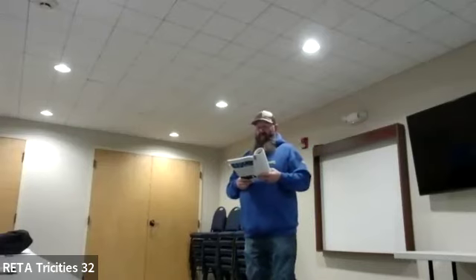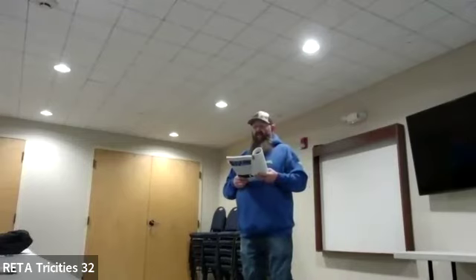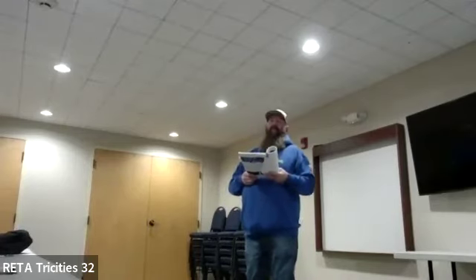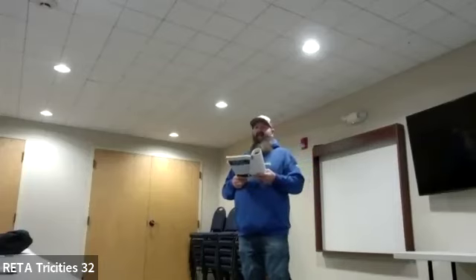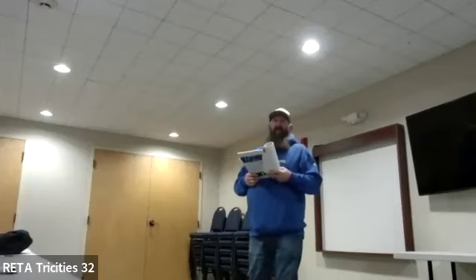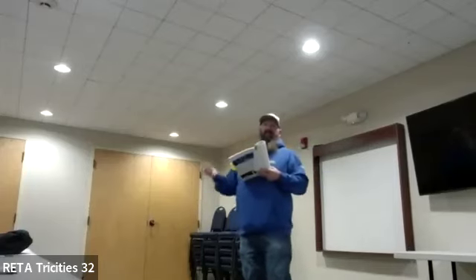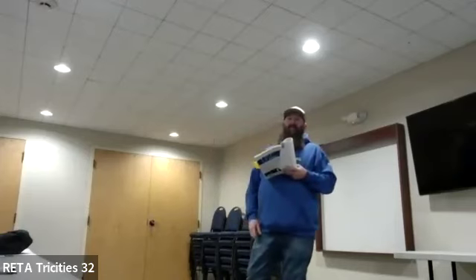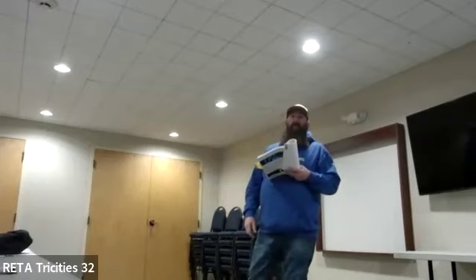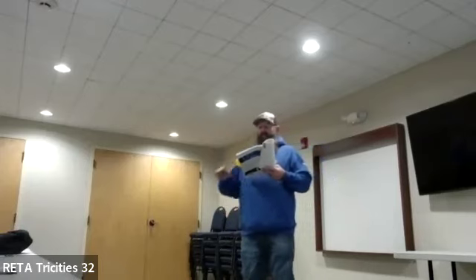Ventilation. I feel there's nothing new, but I feel they threw a little quirk in there, which is verifying automatic function of your temperature control ventilation. And what I mean by quirk is, are we capturing that? Whether you have an occupancy fan or a continuous running fan for temp control, are you testing each temperature zone out? Say you have multiple fans kicking on at different times?